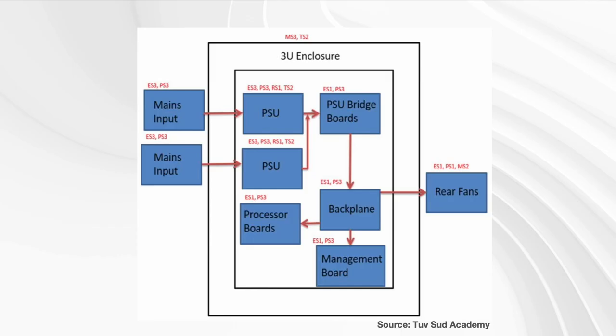It's very useful when designing a new product to have a block diagram like this and to think about energy levels. Here you can see ES3 — mains input is always ES3. You also see PS, which is for flammability, thermal, etc. You need to think of different types of energy, not just electrical energy.